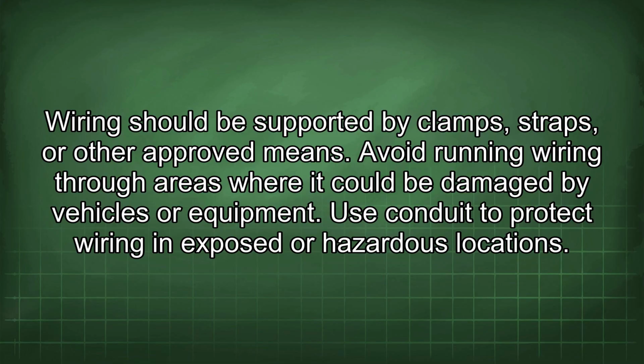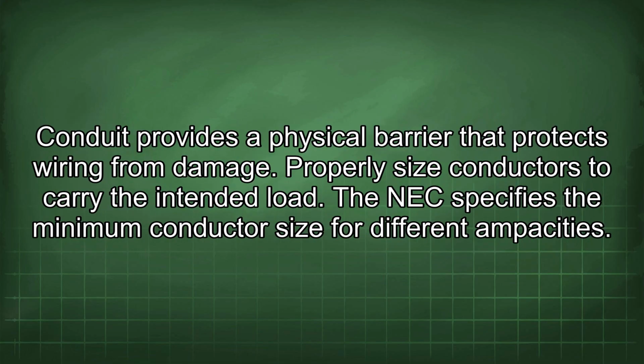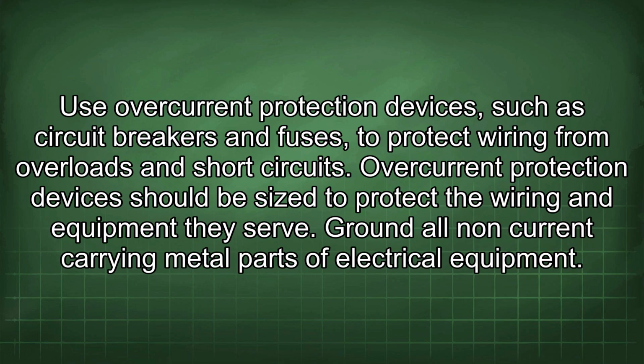Use conduit to protect wiring in exposed or hazardous locations. Conduit provides a physical barrier that protects wiring from damage. Use properly sized conductors to carry the intended load. The NEC specifies the minimum conductor size for different ampacities. Use overcurrent protection devices such as circuit breakers and fuses to protect wiring from overloads and short circuits. Overcurrent protection devices should be sized to protect the wiring and equipment they serve.